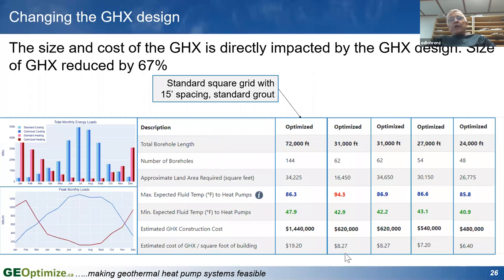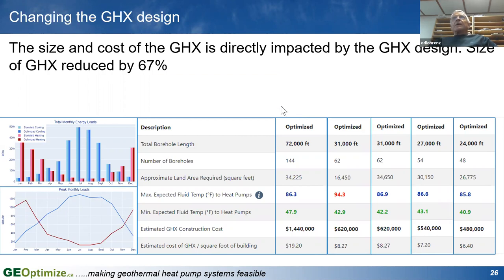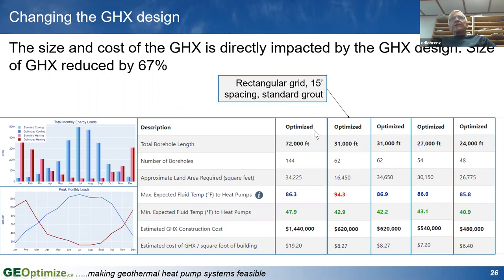The other thing that makes a difference is how you're designing the ground heat exchanger. The space between the boreholes has an impact on how much the boreholes are going to interfere with each other. You shove a whole bunch of heat into the dirt, that's going to dissipate into the ground gradually, and if you've got another borehole right next to it, that's going to raise the temperature of that whole mass of dirt. So if you space that out a bit farther, and look at changing the way the layout is, this is a square grid. This is a grid that's maybe 2x30 boreholes. This is 12x12 boreholes. 72,000 feet of drilling to 31,000 feet of drilling. You're looking at cutting the cost by more than half, simply by how you've designed and laid out the borehole field.